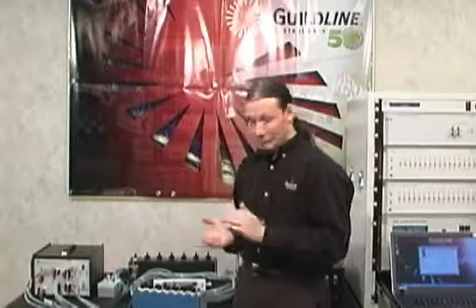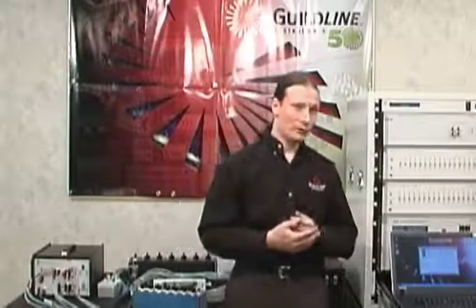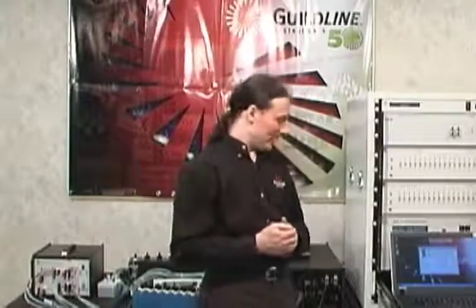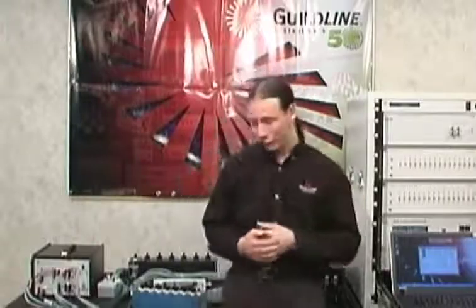And essentially that's it with this utility. You can save these results and bring them back for later recall, and maintain it as your traceability logs for this SR1010.